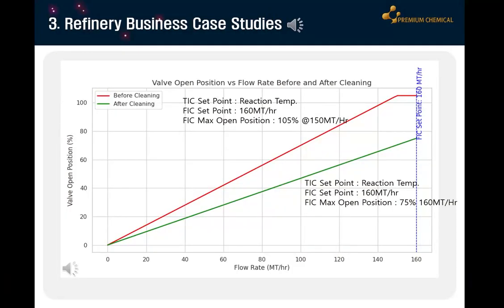Looking at the red graph for the pre-cleaning condition, the flow control threshold is 160 tons per hour. At a flow rate of 150 tons, the valve must be opened to a maximum of 105% to achieve the desired flow rate. This means the valve must be opened excessively to achieve control, indicating internal contamination or severe flow resistance. Let's examine the green graph for the post-cleaning condition.